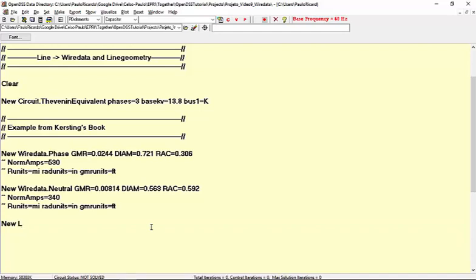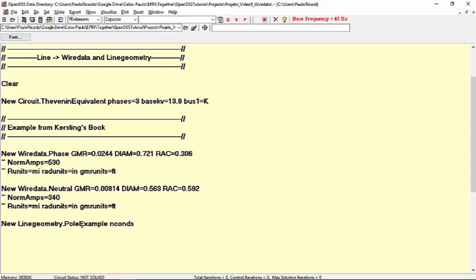In our example, we have only one geometrical configuration, which includes three phase conductors and one neutral conductor. Let's name our LineGeometry as PoleExample. It has four conductors, including three phases. This distinction is important, as we will see later when we talk about Kron reduction.